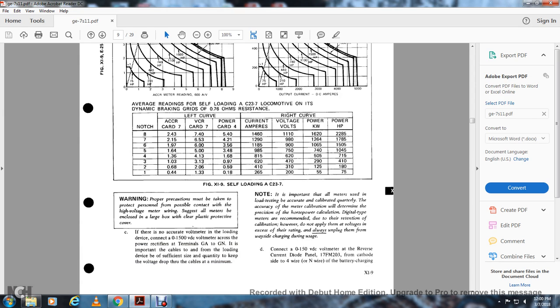Warning: proper precautions must be taken for anyone with possible contact with high voltage meter wiring. Suggest enclosing all the meters in a large box with a clear plastic protective cover. If there is no accurate voltmeter loading with the device, connect a 0 to 1500 volt DC voltmeter across the power rectifier terminals GA to GN.